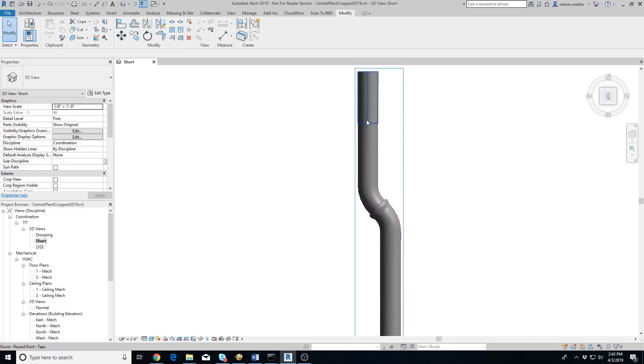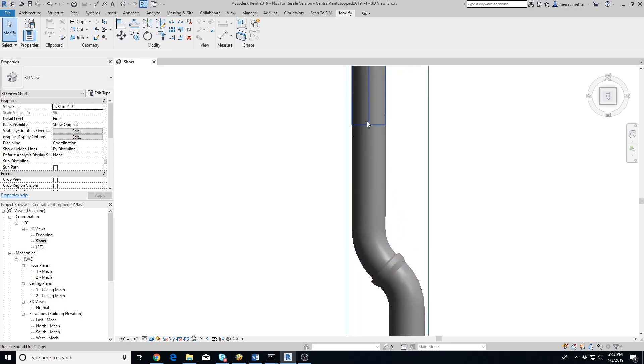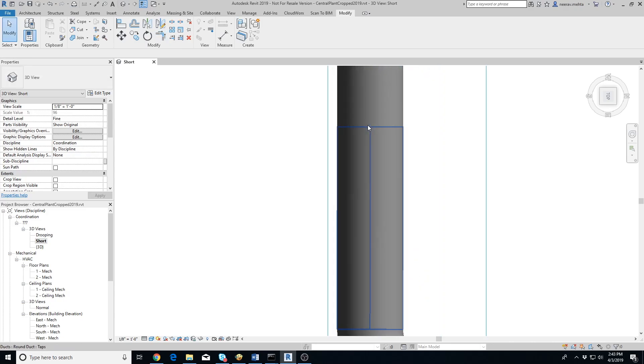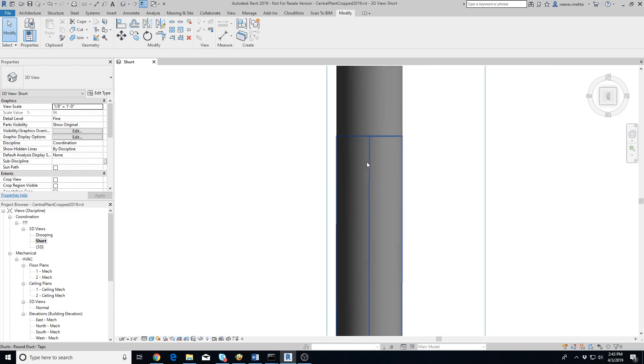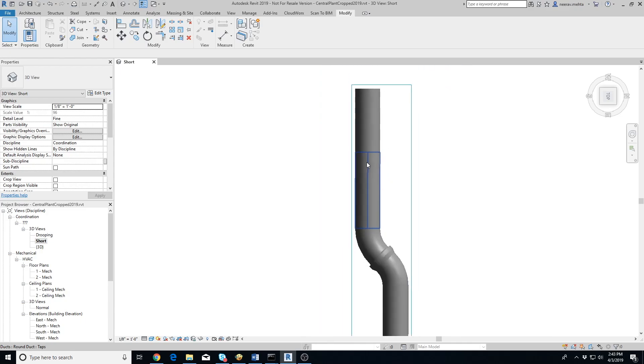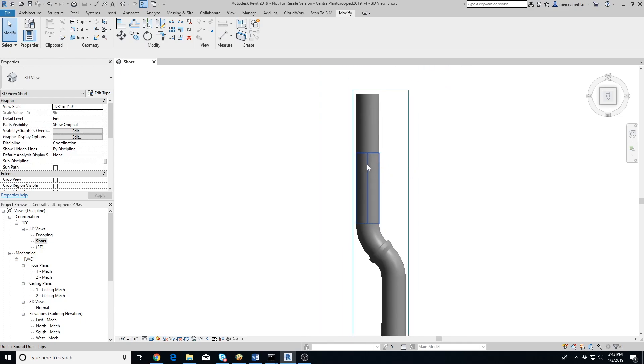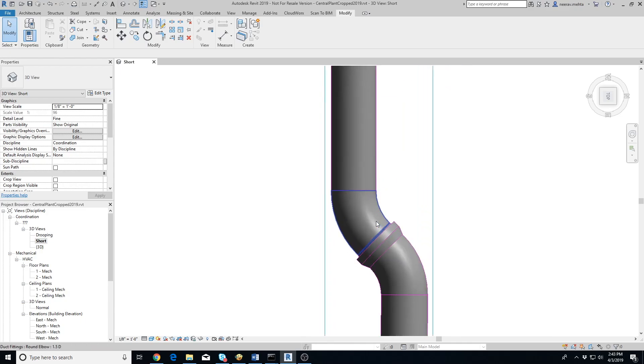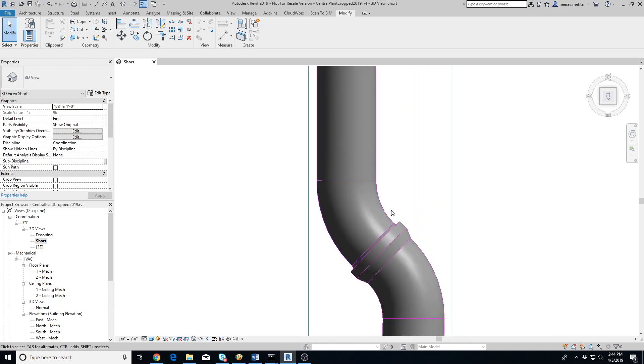Let's check the connection on the top where we had to split up a single duct into two different segments. The Align and Connect tool has connected them as well. The other connection has also automatically been created using a reducer and an elbow.